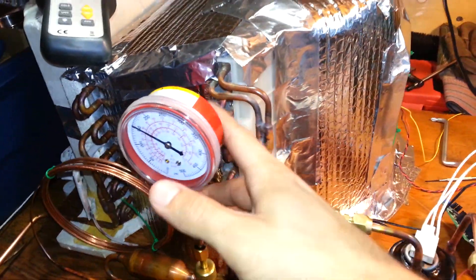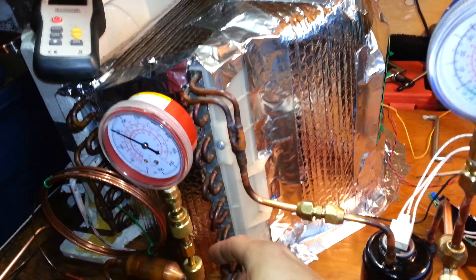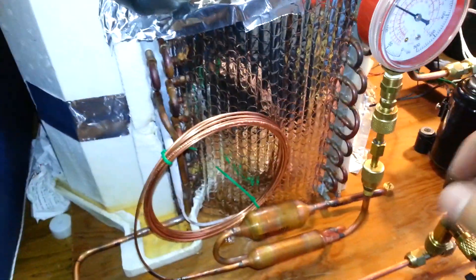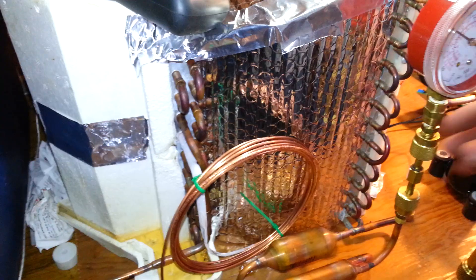And probably even colder until the end as air passes across the evaporator and then cools the condenser. It's ultimately sub-cooling here. So probably only condensation is occurring right up in here in this top portion of the condenser. The remainder of it is sub-cooling, the way I'm interpreting this.